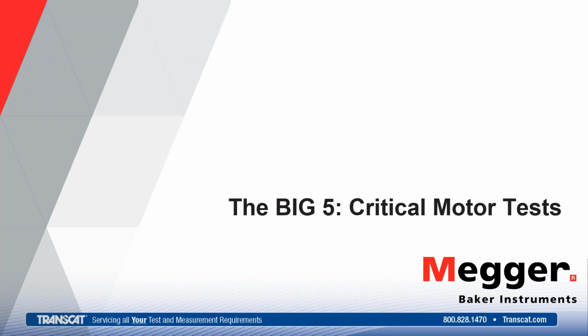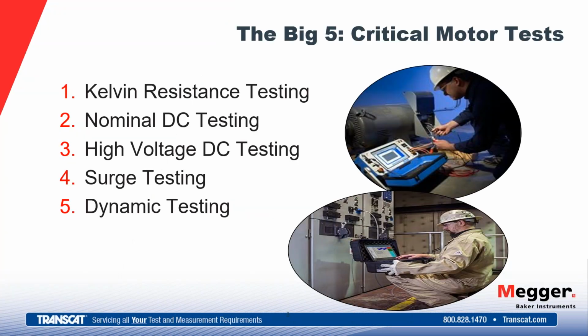As far as we do motor testing, I would consider there being 5 critical tests that should be performed in order to assess the installation integrity of the motor and its environment in which it's living. So we're going to take a look at those 5 critical tests, the big 5 here. The first one is Kelvin resistance testing. Here we're taking resistive measurements from phase to phase and evaluating the resistive imbalance of that motor. And this is considered a low voltage test.